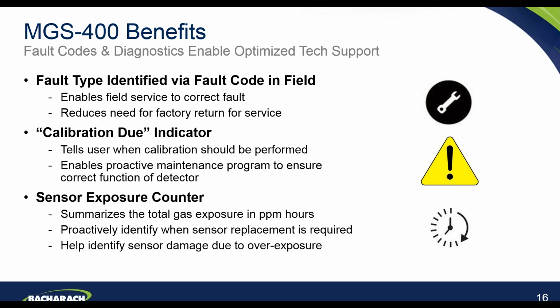The 400 series will provide a calibration due indicator utilizing the app or through the Modbus interface. So this essentially tells the customer when the calibration is due to be performed. And the benefit this brings is that it enables very much a proactive maintenance program to ensure that the detector is functioning correctly. And importantly too, particularly for us here in Europe, it ensures additional compliance with regard to F-gas in terms of ensuring that the gas detectors are maintained annually as per the requirements.